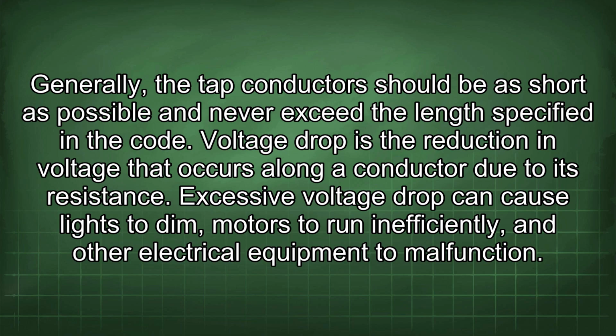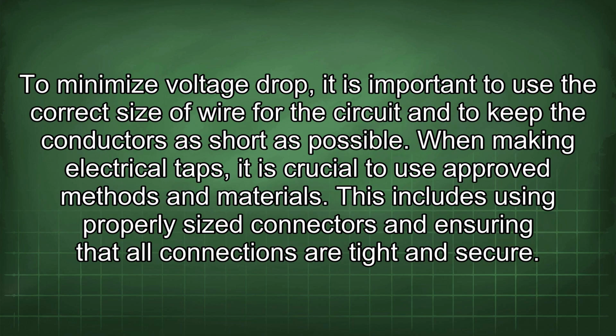Voltage drop is the reduction in voltage that occurs along a conductor due to its resistance. Excessive voltage drop can cause lights to dim, motors to run inefficiently, and other electrical equipment to malfunction. To minimize voltage drop, it is important to use the correct size of wire for the circuit and to keep the conductors as short as possible.